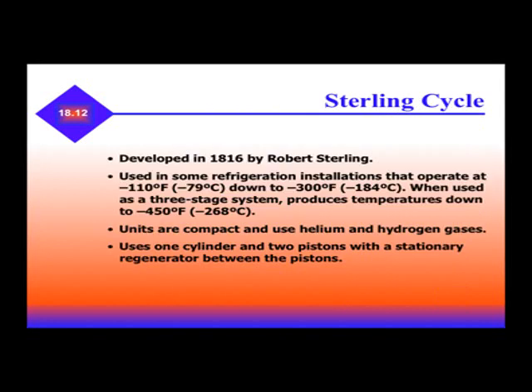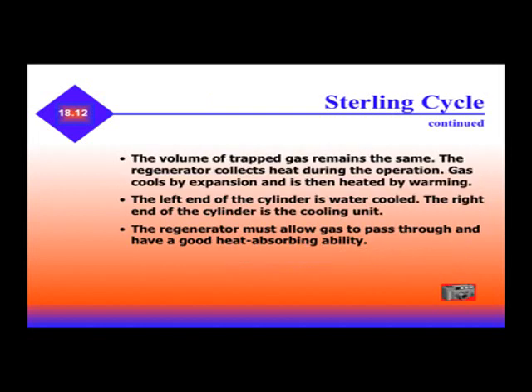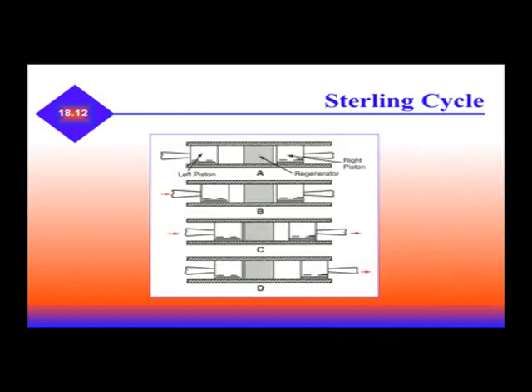We also need to mention the Stirling cycle, developed in 1816 by Robert Stirling. It's used in some refrigeration installations operating at negative 110 down to negative 300 degrees. When used as a three-stage system, it produces temperatures down to negative 450 degrees. The units are compact and use helium and hydrogen gases. It uses one cylinder and two pistons with a stationary regenerator between the pistons. The volume of the trapped gas remains the same. The regenerator collects heat during operation, gas cools by expansion and is then heated by warming. The left end of the cylinder is water-cooled, and the right end is the cooled unit. This is an example of the Stirling cycle, showing a left piston and a right piston.